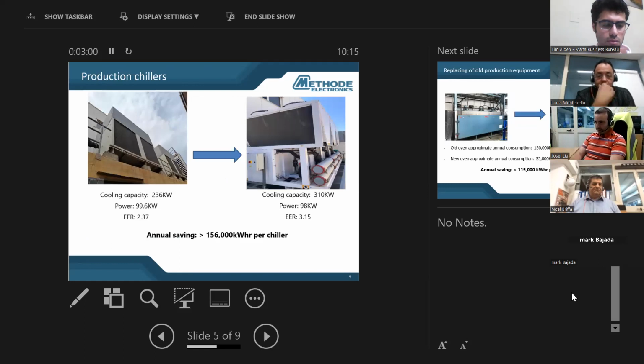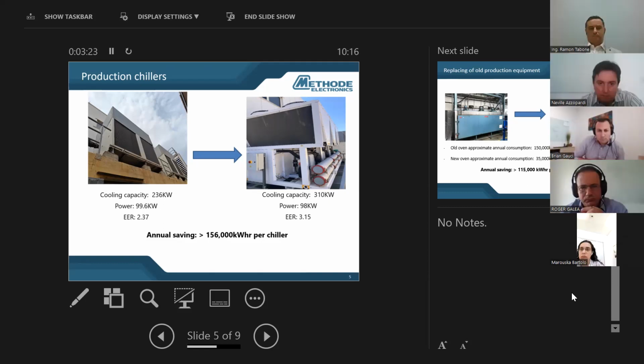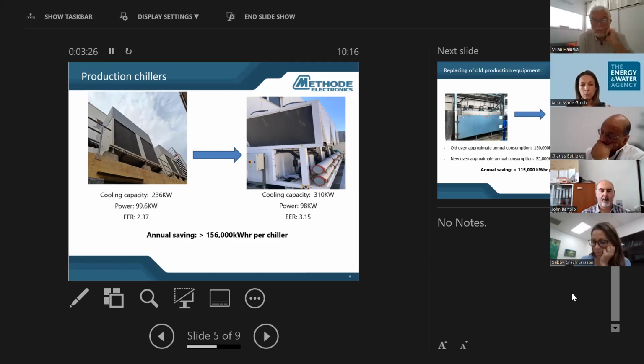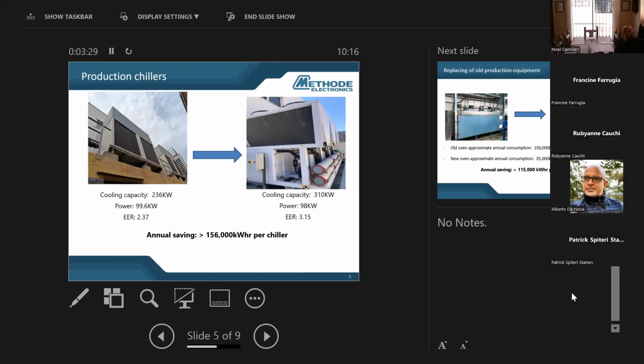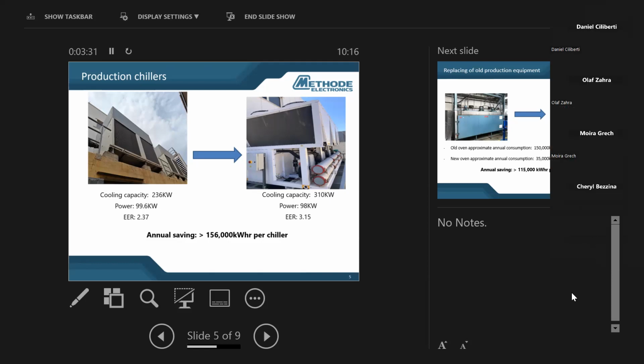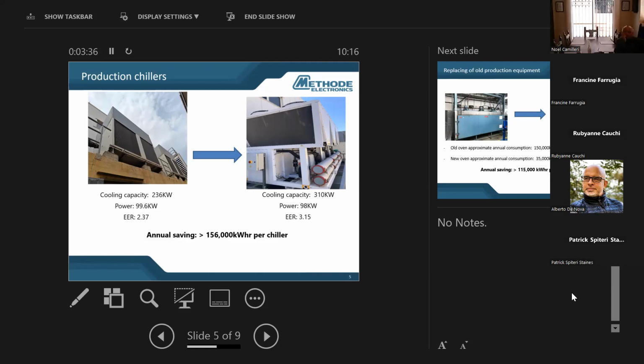Also, recently we have seen that the production chillers have been quite old. They have been running for a number of years, and although they were still running, they were not energy saving compared with the chillers on the market. By replacing the chillers alone, we calculated that we're going to make a saving of around 160,000 units per chiller per year. We have 4 chillers in total, and basically it's quite a significant saving.